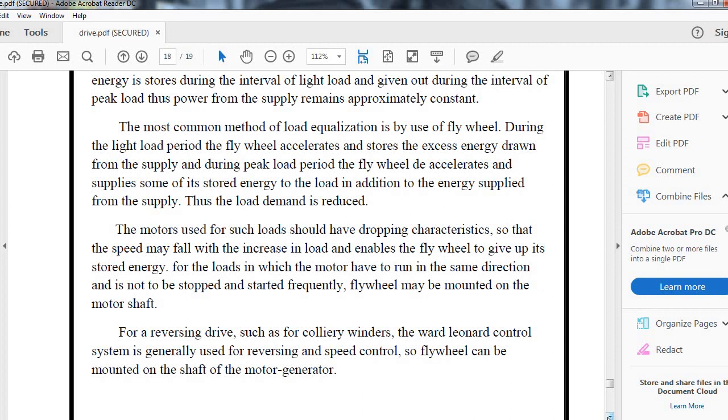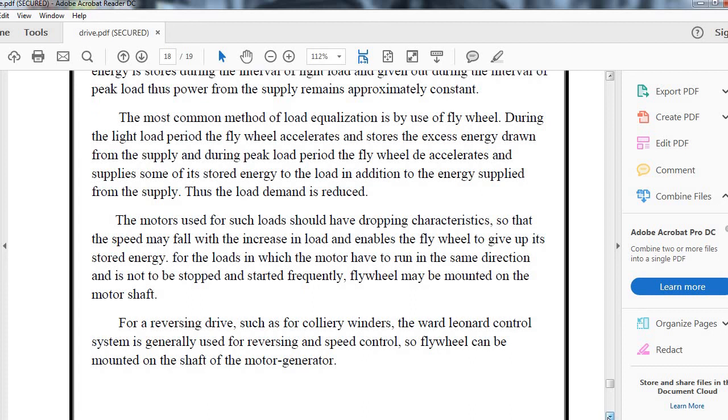For loads in which motors run in the same direction and are not stopped and started frequently, the flywheel may be mounted on the motor shaft. For reverse drives such as Ward-Leonard control system used for reversing speed control, the flywheel should be mounted on the shaft of the motor-generator set.